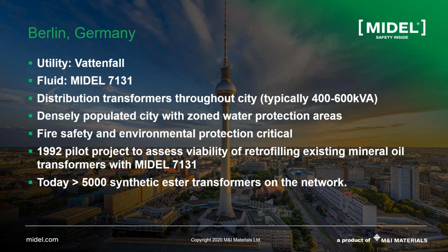And they wanted to use a readily biodegradable fluid, which is also oxidation stable. They used MIDEL 7131 synthetic ester. And so from that time, these transformers are distribution size transformers, typically 400 kVA to 600 kVA. And from 1992 up to now, they retrofilled more than 5,000 transformers with synthetic ester.